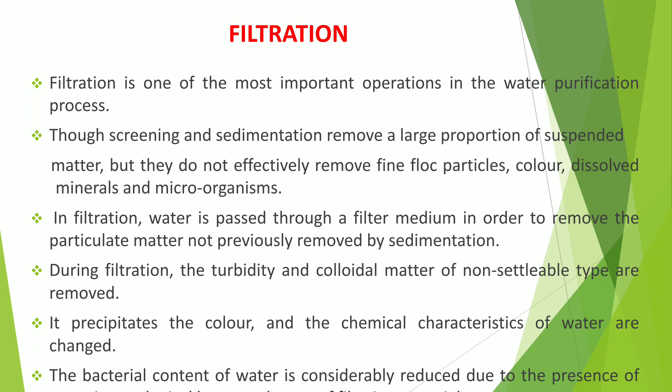However, these processes do not effectively remove fine floc particles, color, dissolved minerals, and microorganisms. To remove those, you have to go for the filtration process. In filtration, water is passed through a filter medium in order to remove particulate matter not previously removed by sedimentation. During filtration, turbidity and colloidal matter of non-settleable type particles are removed. The color and chemical characteristics of water are changed, and the biological content of water is considerably reduced.